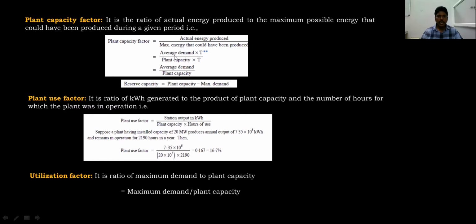So here, from the previous formula, we know that actual energy generated is average demand into time, divided by the energy it can generate, which is plant capacity into time. Plant capacity into time gives you the maximum energy it can generate in a year. So the T and T cancel, and the final result is average demand divided by plant capacity.